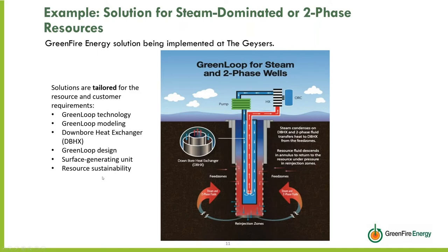...the hydrostatic pressure of the condensate is sufficient to push the steam, which is now actually liquid, back into the resource. This has a great benefit for sustainability, avoiding decline in the resource, which a traditional flash system will cause because the water is coming to the surface and you lose the water at the surface. This approach only brings the heat to the surface with a working fluid. All of the resource fluid, steam or two-phase fluids, stay in the resource, so you don't need injection wells.